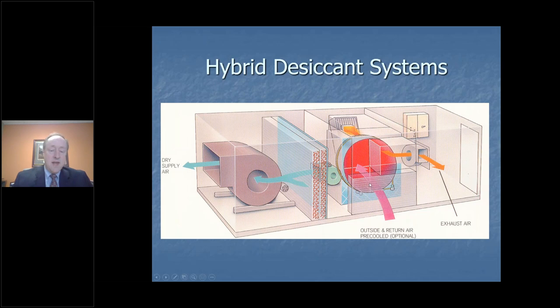Now we can take it from that point and go through the wheel and do the deep drying. I could do it all with the wheel, but it would be a much larger wheel. It would require much more energy, but this is a much more efficient way of doing it. So let's pre-cool with the coils, really we're pre-dehumidifying, get moisture out here, then get moisture out there, and then we'll heat or cool as necessary downstream to send that drier air into the space.